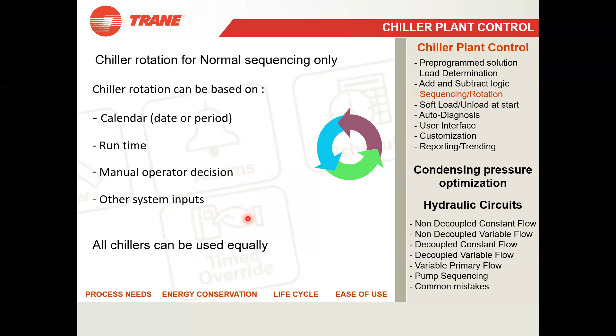So now one more thing is soft load. I want you all to understand what this is. This is a very important feature of chiller plant control, soft load and unload. So what is soft load? If you have a 9 to 6 kind of operation and you have to switch off everything at night when you are going back home, the facility manager switches off everything and goes back. And in the next morning, he comes at 8 o'clock and has to start the operation, because people will be coming to the office from 8:30 or 9 o'clock. So he has to be ready.